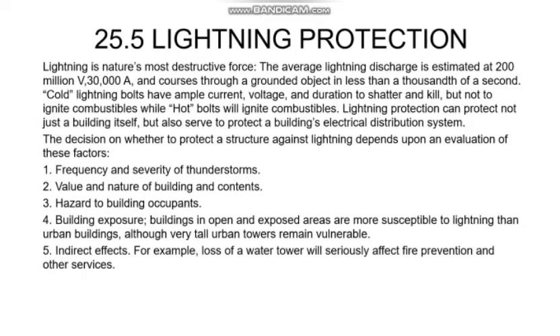Lightning protection can protect not just a building itself, but also serve to protect a building's electrical distribution system. The decision on whether to protect a structure against lightning depends upon an evaluation of these factors. 1. Frequency and severity of thunderstorms. 2. Value and nature of building and contents. 3. Hazard to building occupants. 4. Building exposure. 5. Indirect effects.